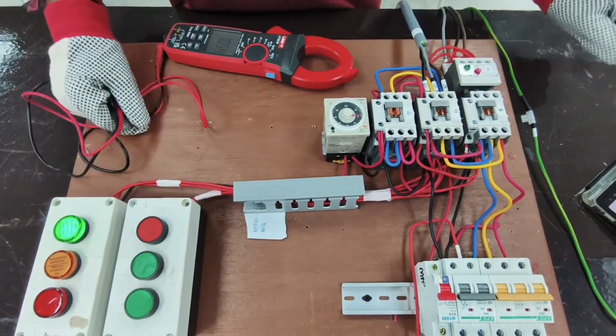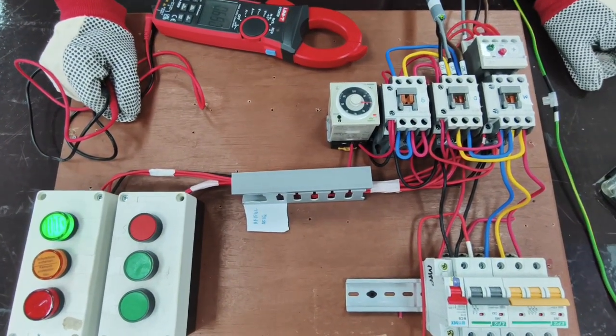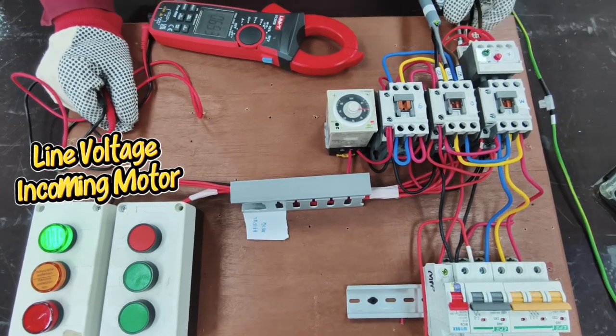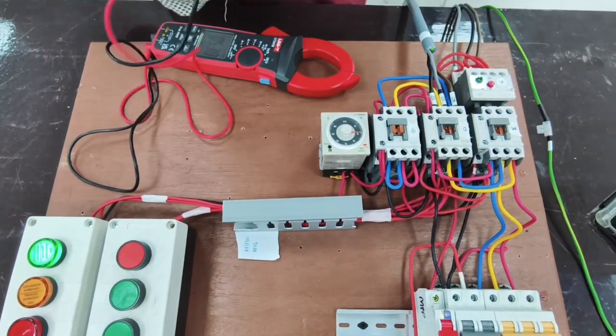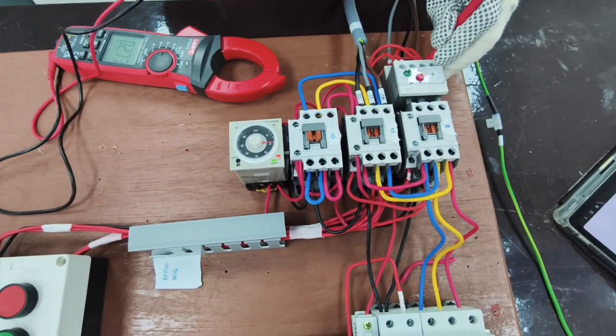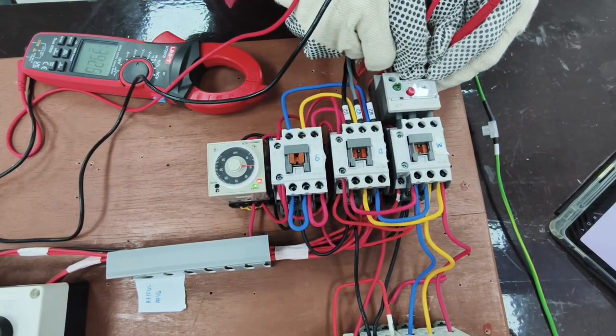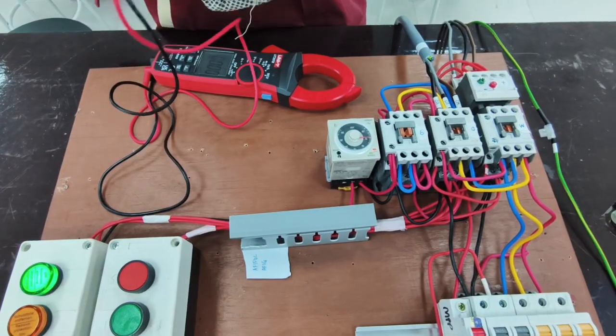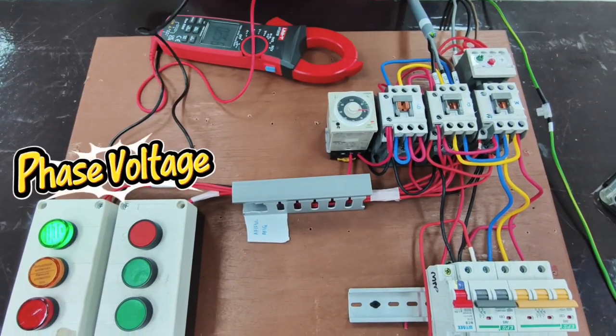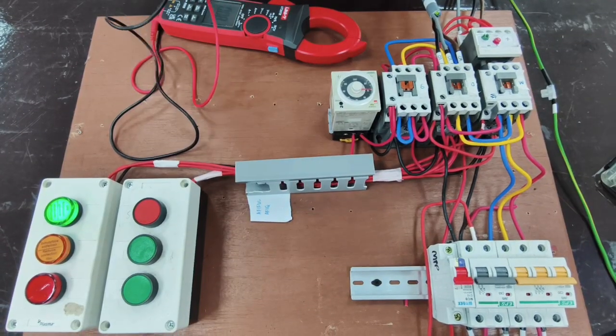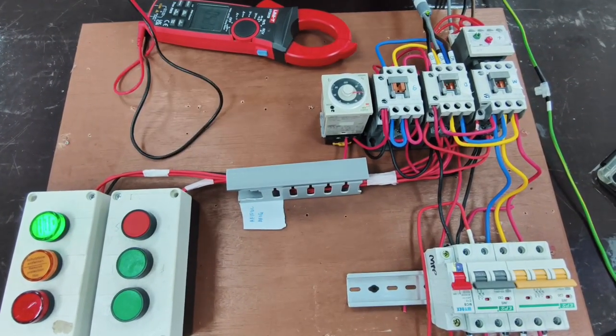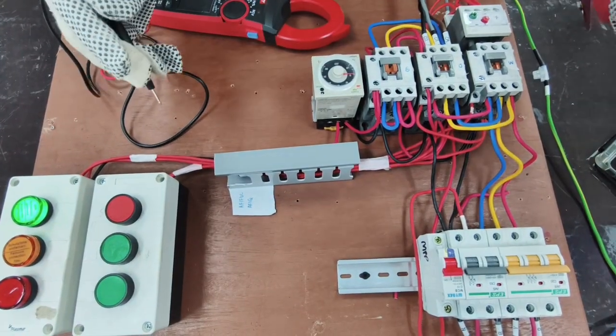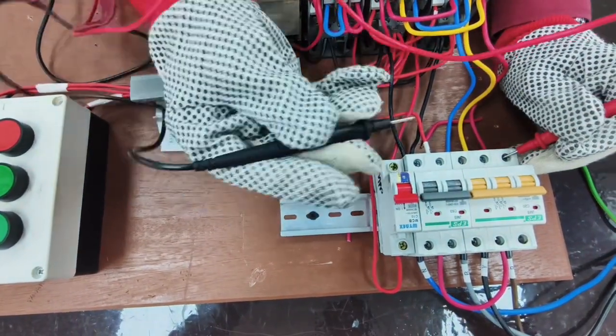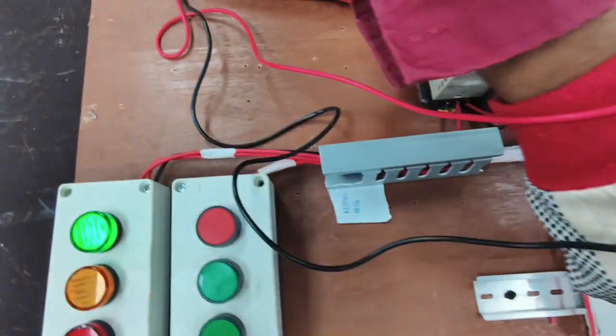And then I will show you how to take the line voltage for the incoming motor. So this is our motor incoming. Same, we just put one on the U1 and one on the V1. So we get 417 also. Then we can take the reading for phase voltage. For the phase voltage, one probe is on our line and one probe on the neutral. This is the phase voltage at the power supply. So one probe at the red and one probe at neutral. Here we got 237 volt.